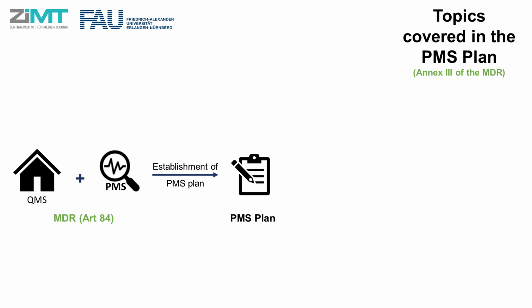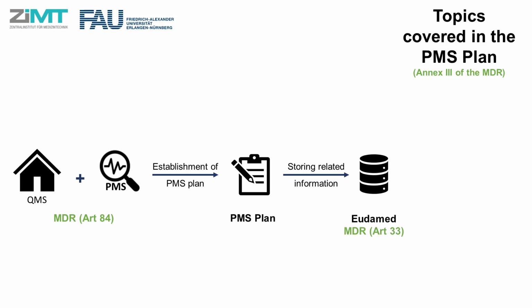dedicated post-market surveillance plan. This document shall describe how the manufacturers update their technical documentation and which actions they shall perform in order to cooperate with the national competent authorities in charge of vigilance and market surveillance activities. The manufacturer shall store information related to the post-market surveillance plan into the dedicated European database, EUDAMED. Article 33 of the new MDR describes all the registration requirements to be uploaded into the database.